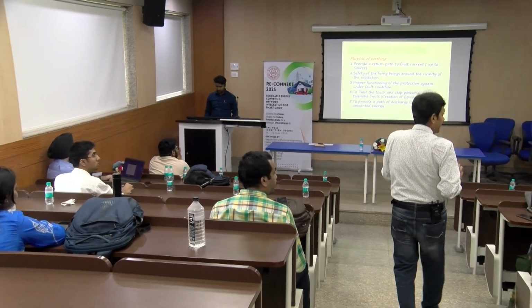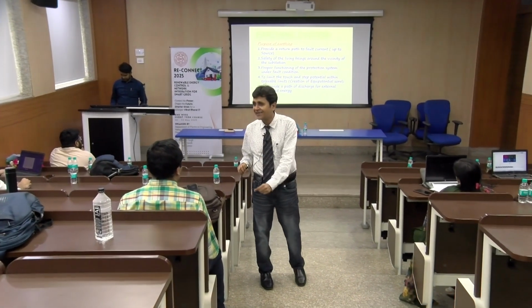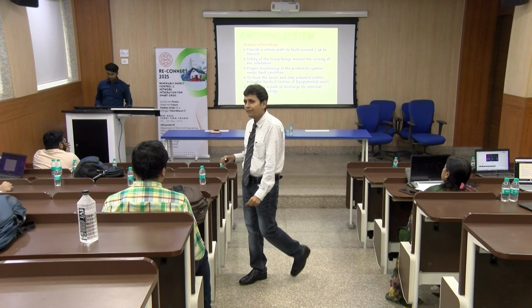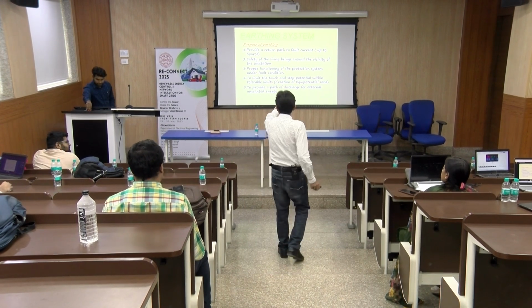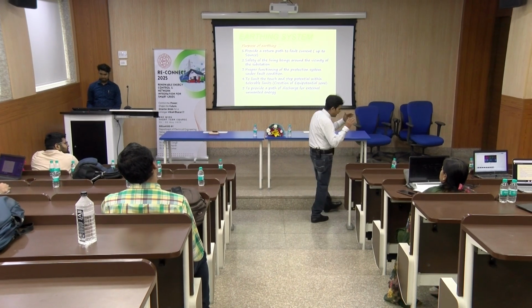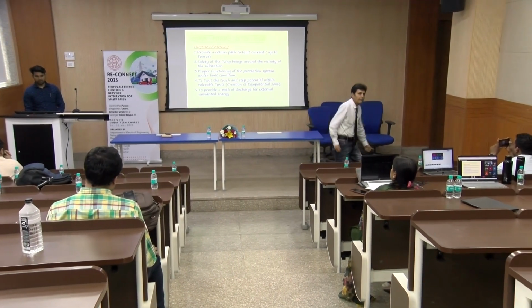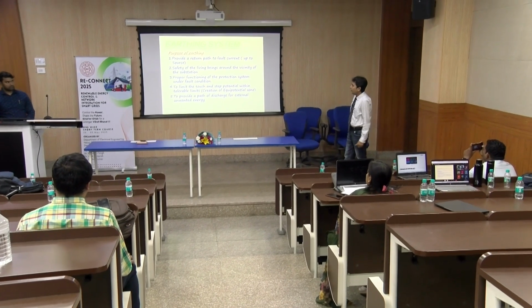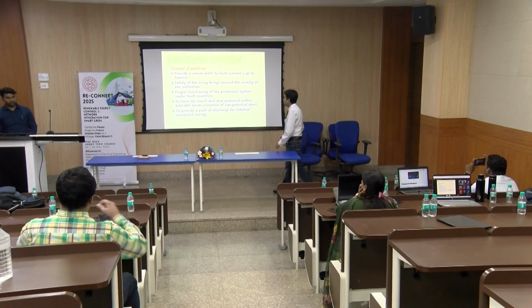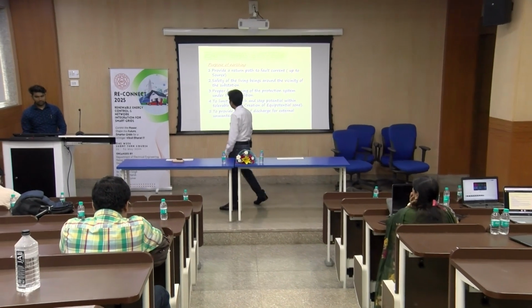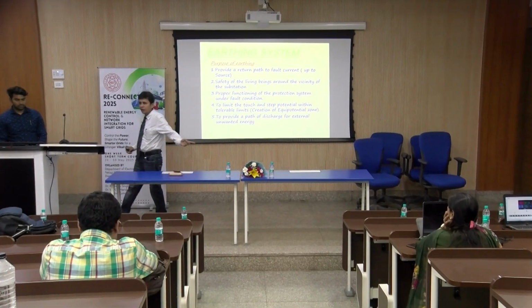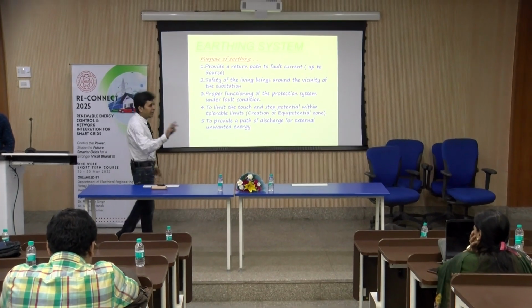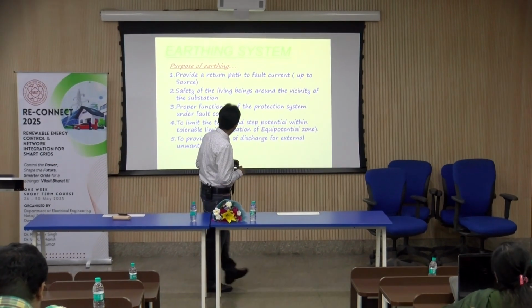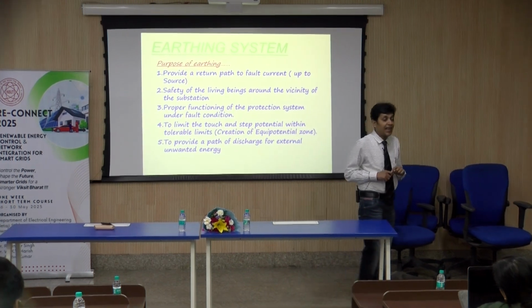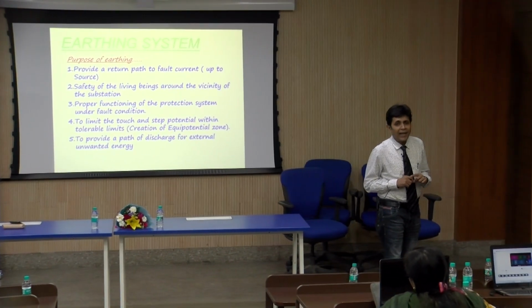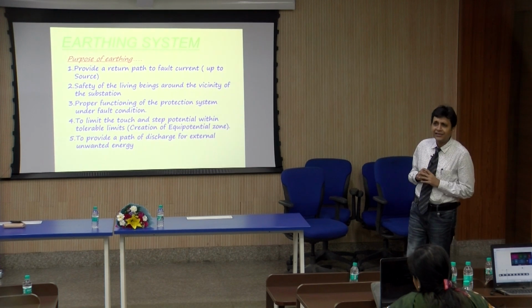It is said that in the absence of earth, the system becomes unearthed, and unearthed is a disaster. Earthing provides a return path for the fault current back to the source. It provides safety of living beings around the vicinity of substations and the systems you are working with. It ensures the proper functioning of your protective relays, and it limits the touch potential and the step potential. Last but not least, it takes care of the lightning discharges that may attack or strike your structures.